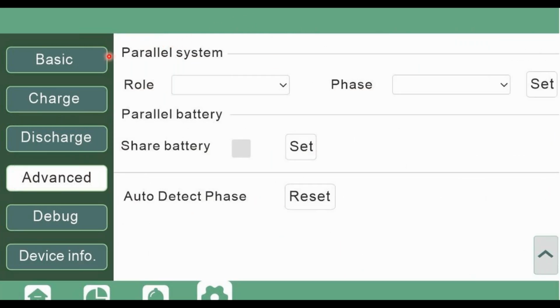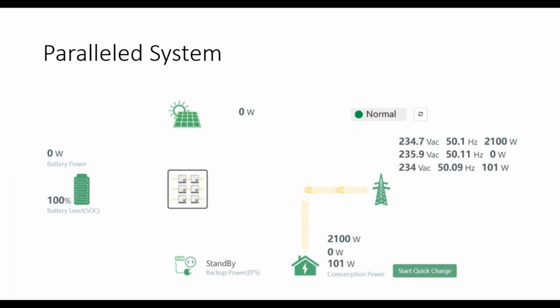And then last but not least, here's the paralleling system in the advanced section, where you would designate the role of the inverter, whether that's master or slave, and what phase it is. It has a cool feature where it says auto detect phase: if you have three phase, and assuming it's connected properly, you would just click on the reset button and it will designate the correct phase to each inverter. So here is the system as you can view it when paralleled, where you can read the cluster. You have three inverters with their frequency and power being generated.